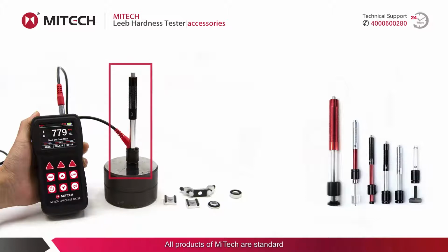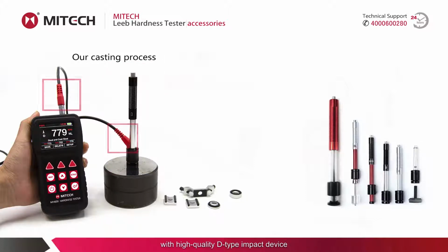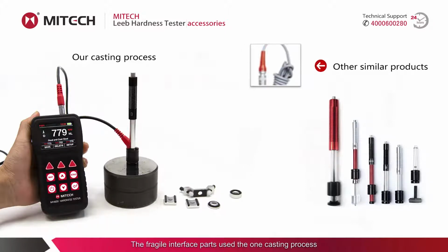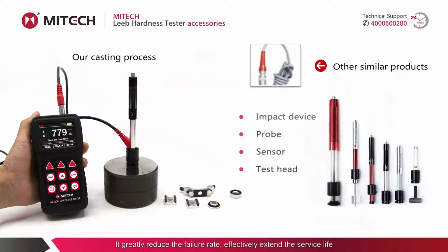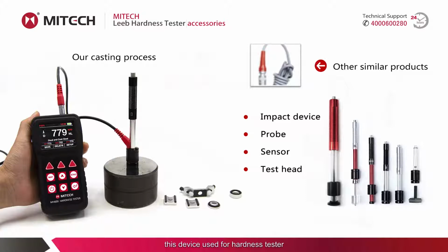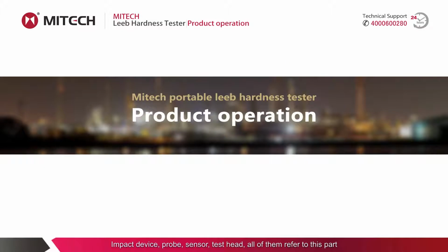All products of Mitech are standard with a high-quality D-type impact device. The fragile interface parts use a one-piece casting process, strong and durable. Compared with other similar products, it greatly reduces the failure rate and effectively extends the service life. This device, used by the hardness tester to collect data, has a variety of names: impact device, probe, sensor, test head, all of them refer to this part. Let's introduce the application of the Mitech hardness tester in detail with a real product.